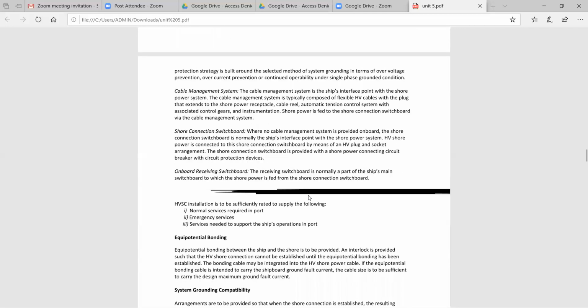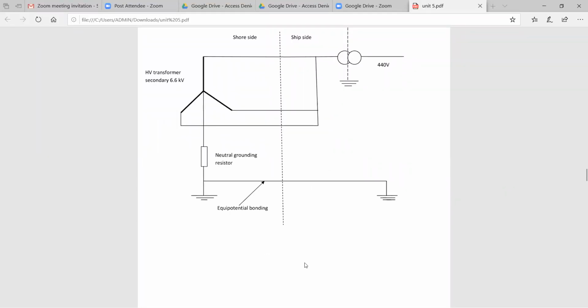Simultaneously, equipotential bonding and system grounding compatibility will be considered. The system grounding concept covers how many generators will be operated on the shore side, and how they can be connected to the ship side with the concept of a neutral grounding resistor. With a neutral grounding resistor mechanism, the connection lines transfer without any leakage or short circuit current, and the neutral line is observed to have zero current flow.